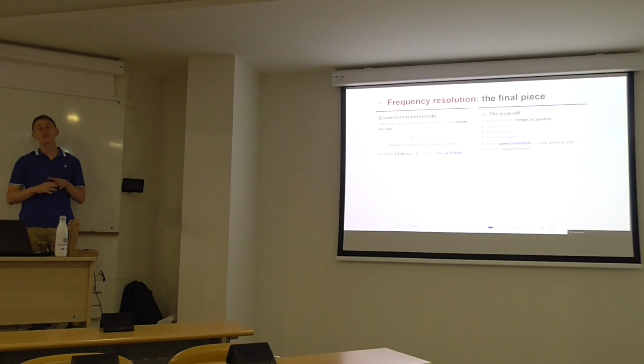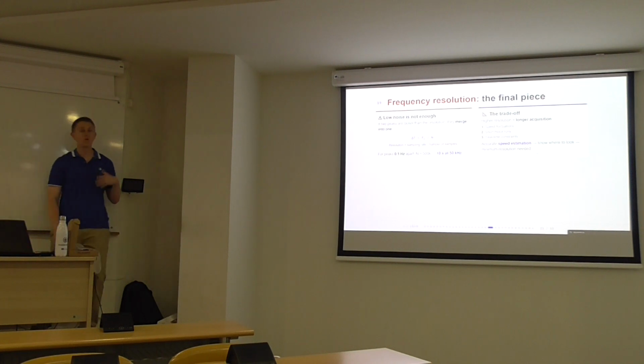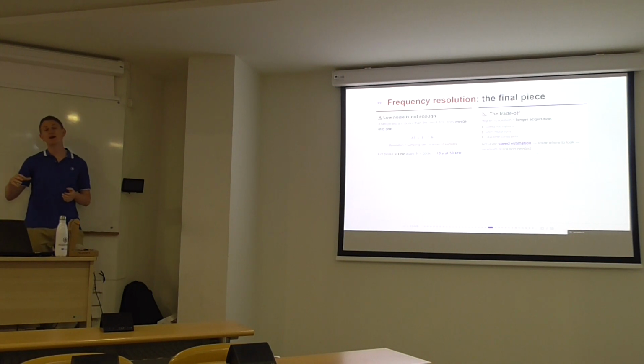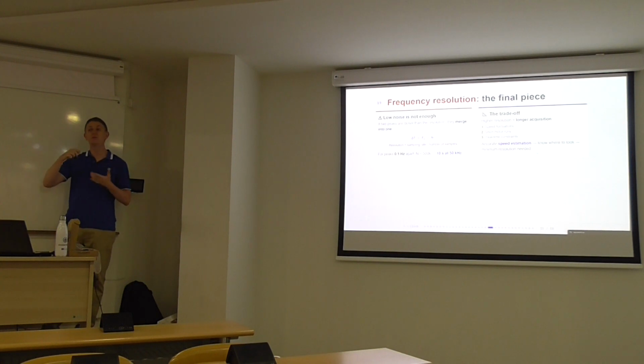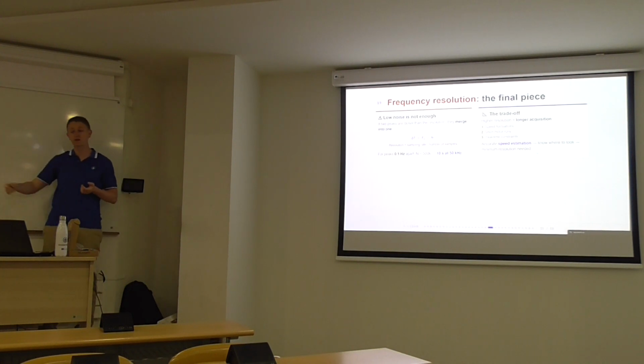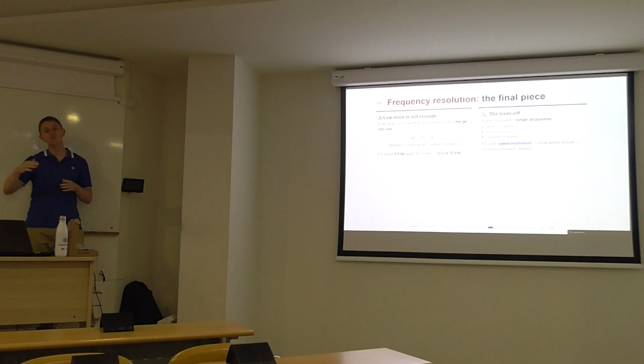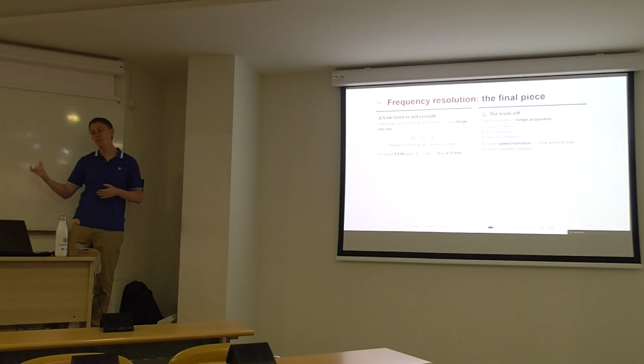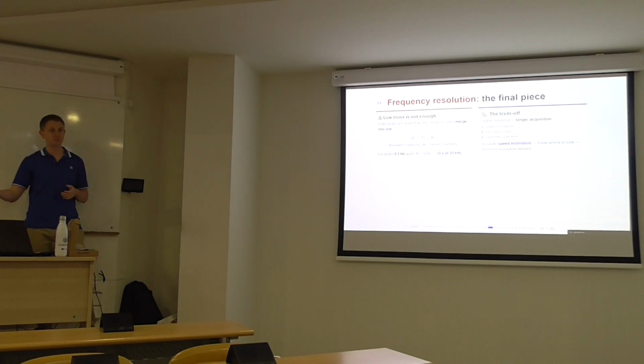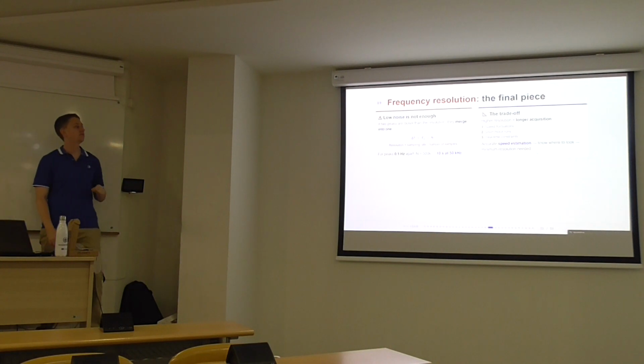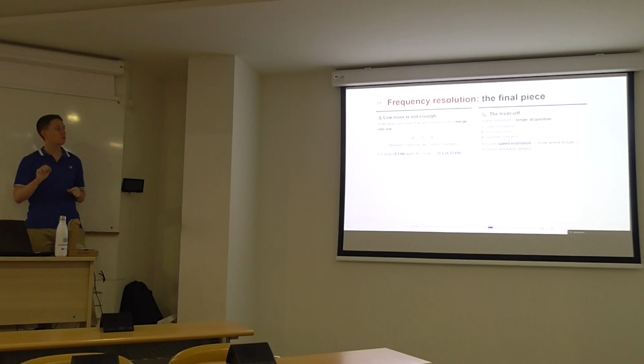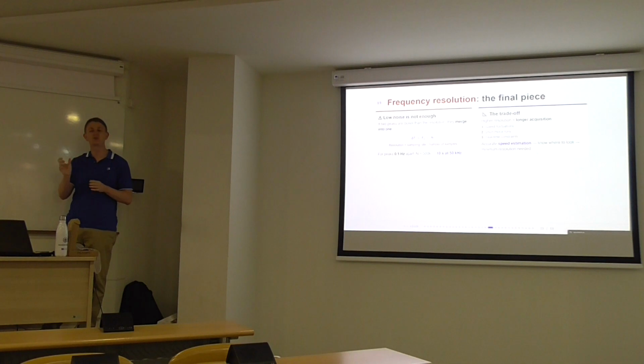So here what we have is a trade-off. If we want higher resolution, we need higher acquisition time. But higher acquisition time implies speed fluctuations. The motor can change load during the recording, there may be short motor runs, maybe the motor stopped during the recording, or there is a real-time constraint if you want to implement a real-time diagnosis system. Okay, there is always a compromise. However, if we have an accurate knowledge of the speed, we know exactly where to look and we can decide what is the minimum resolution required.